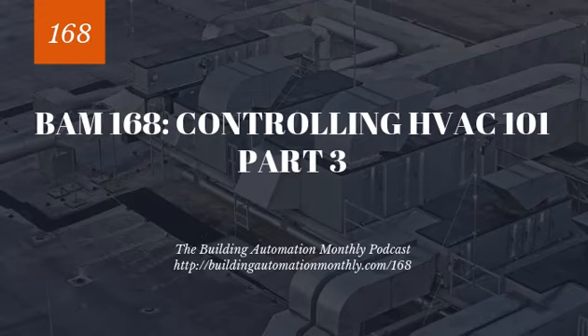So then we're going to take those BTUs per hour and divide them by 12,000, and that's going to give us our tonnage, so our required cooling capacity tonnage. And the rule is that you want to oversize a chiller by about 20%. So I would say whatever that tonnage is times 1.2, which is 100% plus 20%. So that's 1.2, that's 120%.